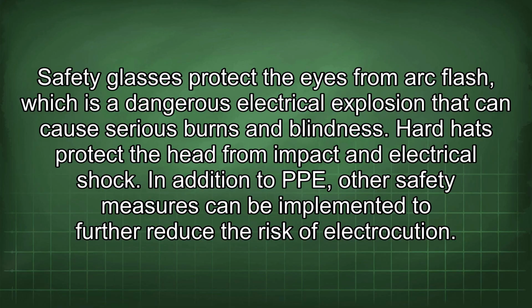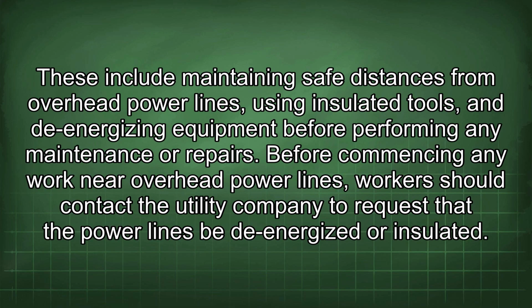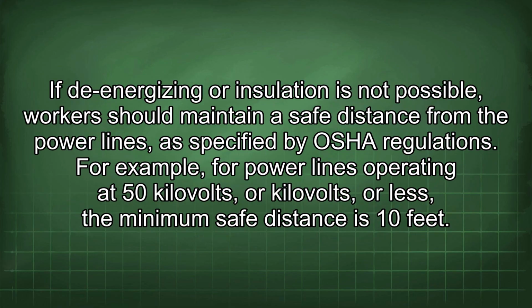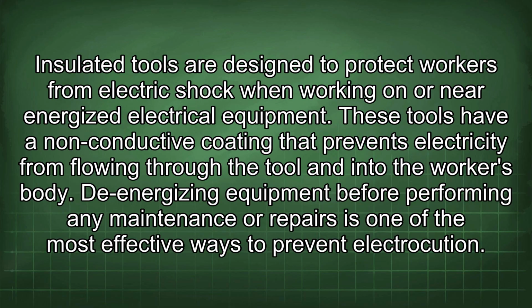In addition to PPE, other safety measures can be implemented to further reduce the risk of electrocution. These include maintaining safe distances from overhead power lines, using insulated tools, and de-energizing equipment before performing any maintenance or repairs. Before commencing any work near overhead power lines, workers should contact the utility company to request that the power lines be de-energized or insulated. If de-energizing or insulation is not possible, workers should maintain a safe distance from the power lines, as specified by OSHA regulations. For example, for power lines operating at 50 kV or less, the minimum safe distance is 10 feet.